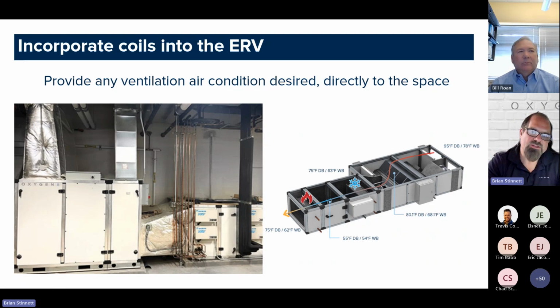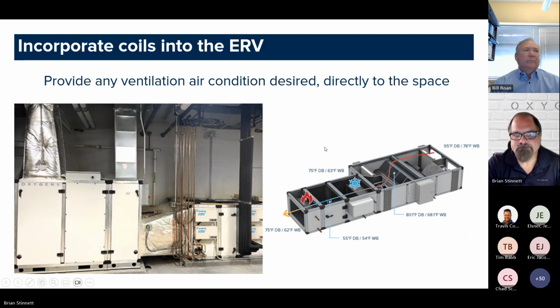So I blow my ventilation air directly into the space, and then I use the rest of the equipment, whether it's fan coils or water source heat pumps or whatever. I use that to strictly handle the space load. So you fully handle the ventilation load with the ERV and coils, and then you handle the space load with the other HVAC equipment.